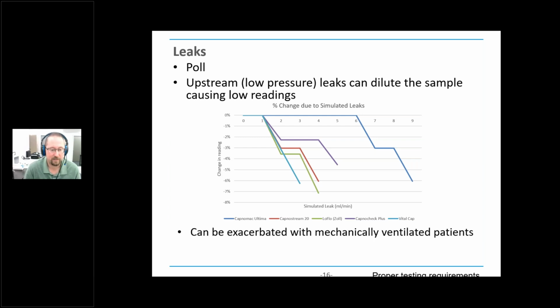And so that's why it's important to always make sure you do a full leak check on your devices. Some of them are easier to do than others. I know the GE devices are a pain to do because you have to kind of take them apart, but it still should be done because leaks can really affect the performance of the device.